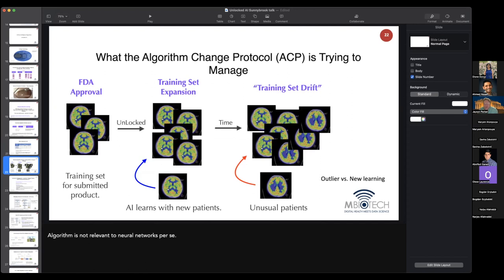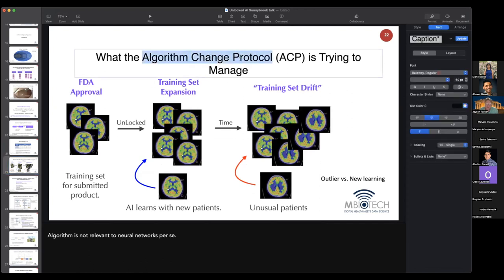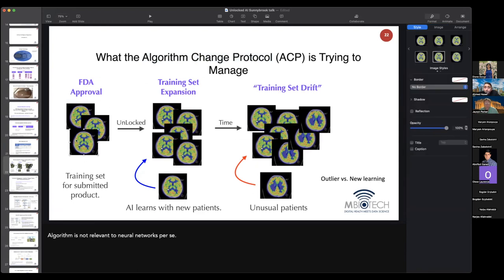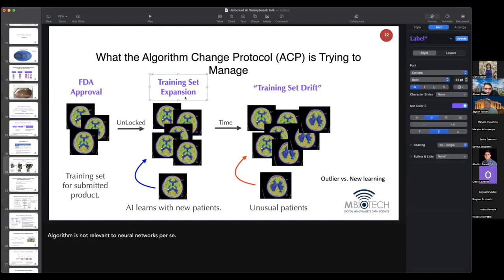What the FDA has talked about is an algorithm change protocol — intended to manage the challenge of an unlocked neural network. Starting with FDA approval of a neural network previously trained on medical images, say stroke detection or identifying aneurysms — in a non-locked scenario, over time we're going to see training set expansion. If the neural network is going to learn, it's going to have to expand its original training set. Additional patient examples added to the original training set over time would expand the sample size and in theory improve clinical decision-making.